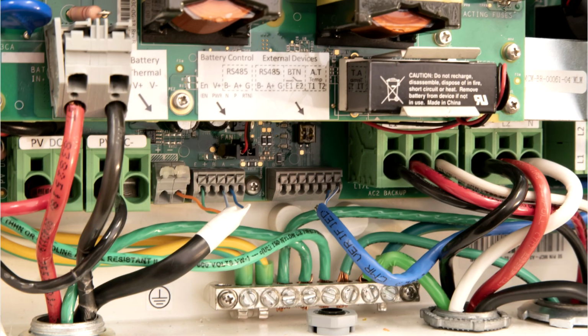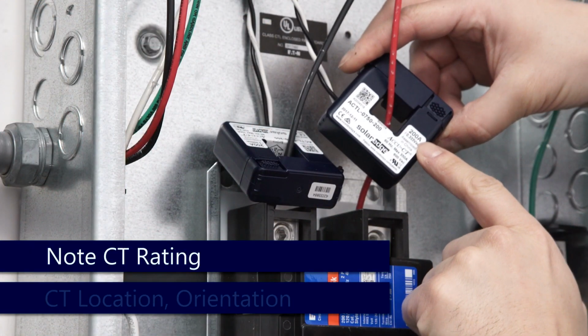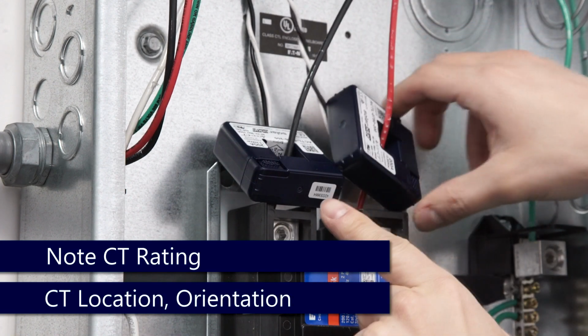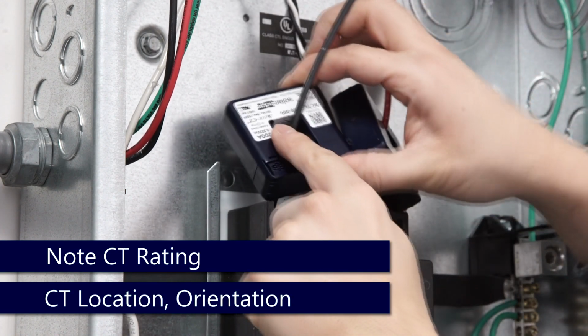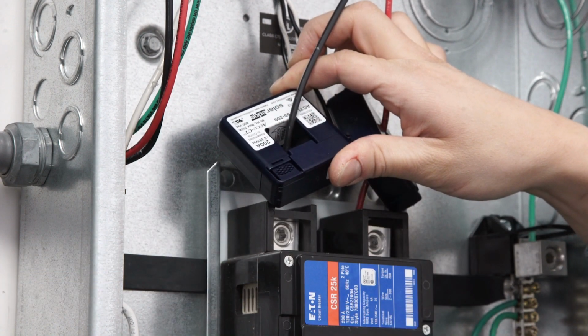Next, CT orientation and location. Note the CT rating and note the source. The source should be pointed towards the utility at the main service entrance.